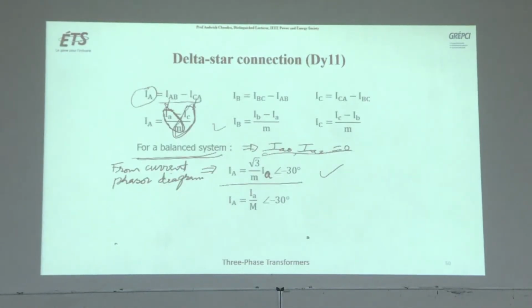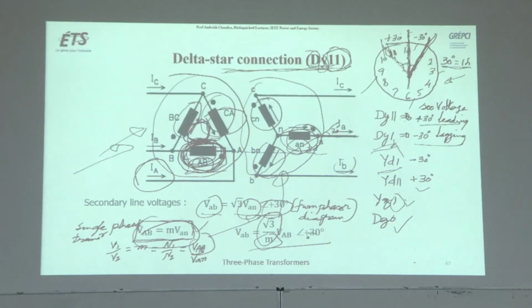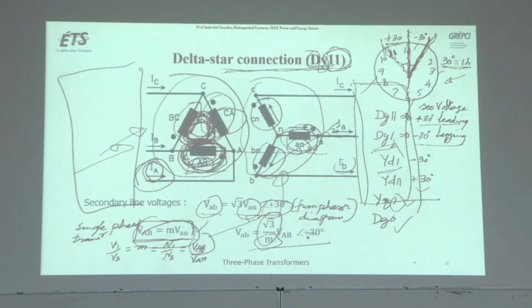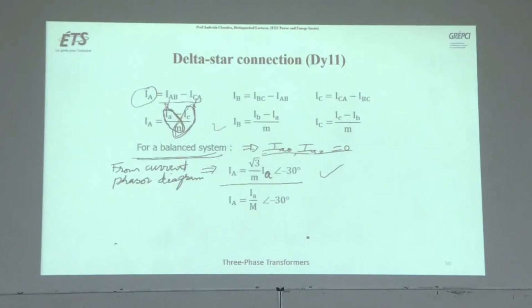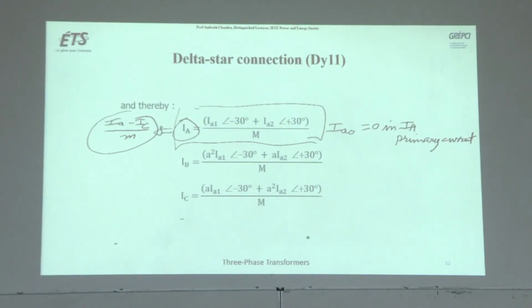It means in this transformer, if you have a non-linear load here, unbalanced non-linear load, so you have all kinds of harmonics and sequences, then zero sequence currents, third harmonic, they are trapped here, but they are not polluting the network here if you are using delta.